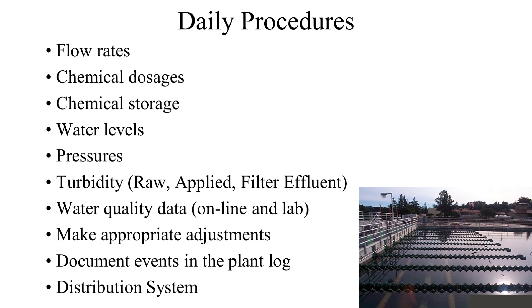However, the operator does more than just monitor the treatment process. Based on water quality data and the need to adjust flows at the plant, an operator must make adjustments. As the raw water quality changes, say due to a rainstorm, the feed rate of the treatment chemicals must be changed. Maybe there is a leak on a chemical tank or a power failure causes a chemical pump to stop. It is the responsibility of the operator to quickly make the appropriate changes to keep the plant in service and continuously meet the regulations. The operator is responsible for accurately documenting the status of the plant and all changes made in the plant log.